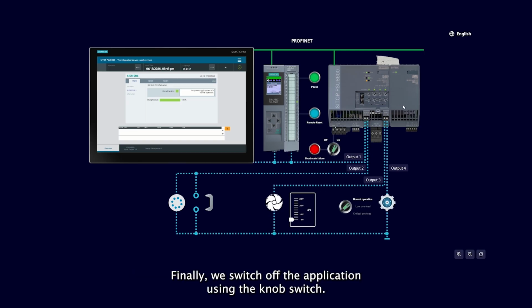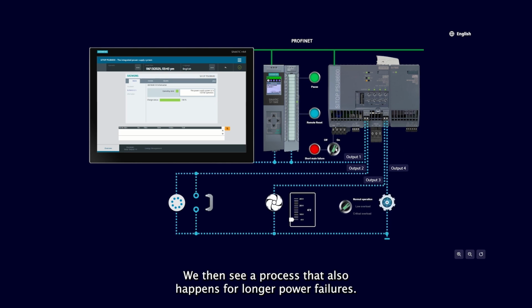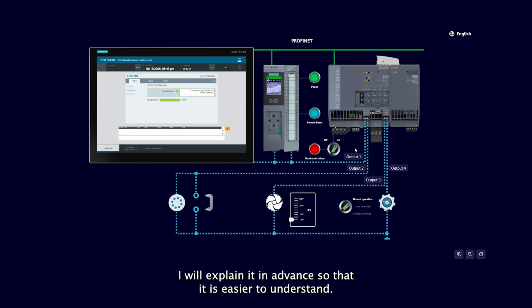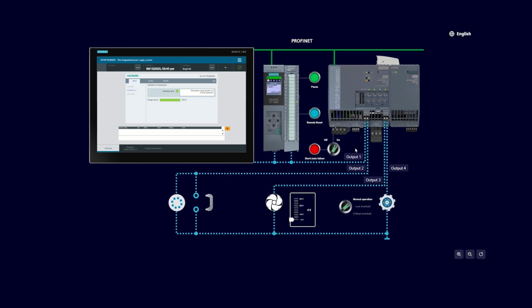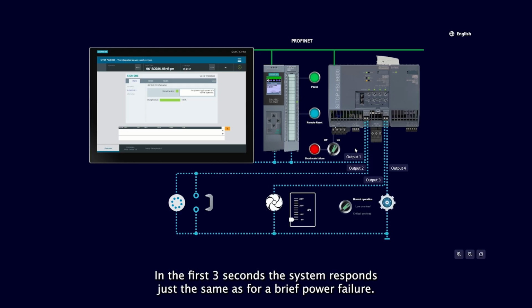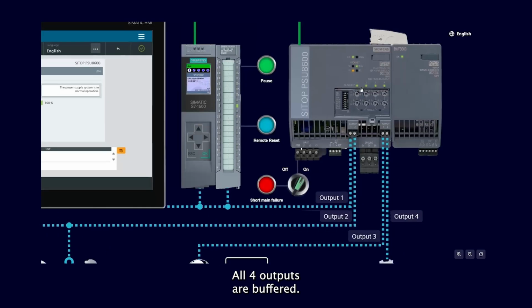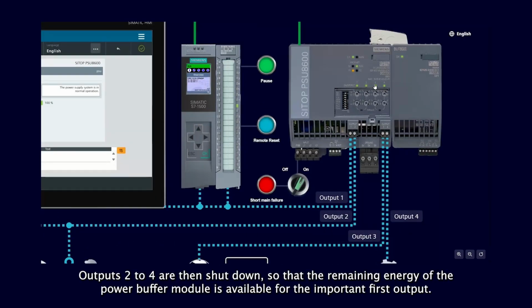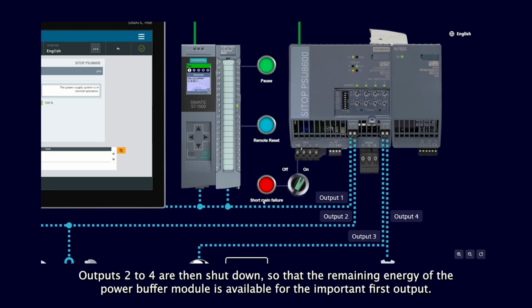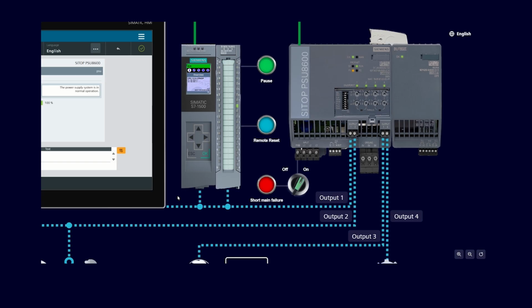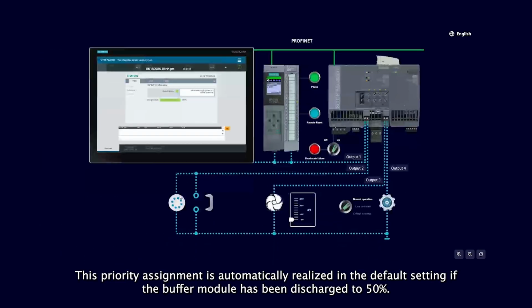Finally, we switch off the application using the knob switch. We then see a process that also happens for longer power failures. I will explain it in advance so that it is easier to understand. In the first 3 seconds, the system responds just the same as for a brief power failure. All 4 outputs are buffered. Outputs 2 to 4 are then shut down so that the remaining energy of the buffer module is available for the important first output. This priority assignment is automatically realized in the default setting if the buffer module has been discharged to 50%.